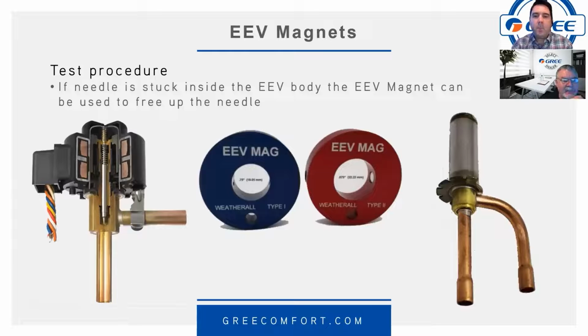So talking about that sticky EEV, these are permanent magnet EEV magnets, and there's 2 sizes because there's a couple different sizes of the body on the EEV valve itself. So these are designed to fit just around those nicely. And you can use these things to turn that piston inside there, just like opening and closing a faucet. And sometimes if there's a piece of debris or something that's causing that thing to stick, you can spin those EEV magnets and loosen that up and maybe free that up. That would be a lot better for me than having to replace this and braze a new one in there.